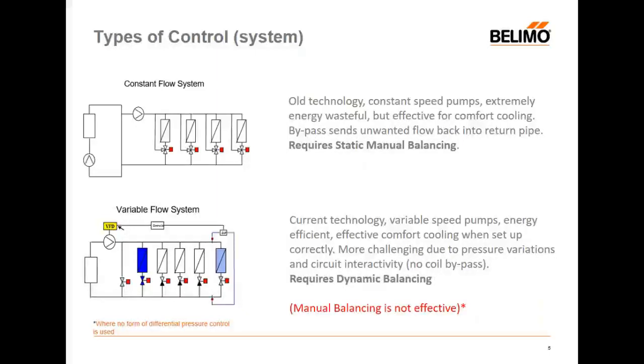As some circuits close, the flow will take the line of least resistance and start to overflow the remaining open circuits. So this interactivity will impact the overall controllability of the system. And if we aren't able to control very well, then we can see underflows in some circuits, certainly overflows in others, and perhaps leading to low delta T syndrome.